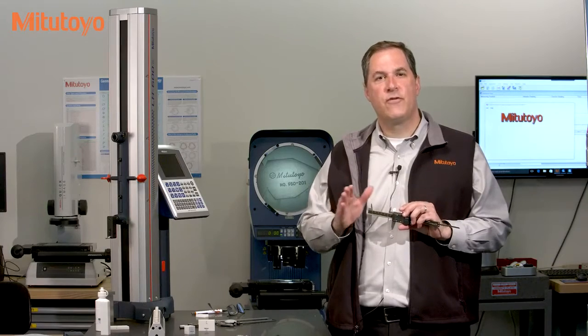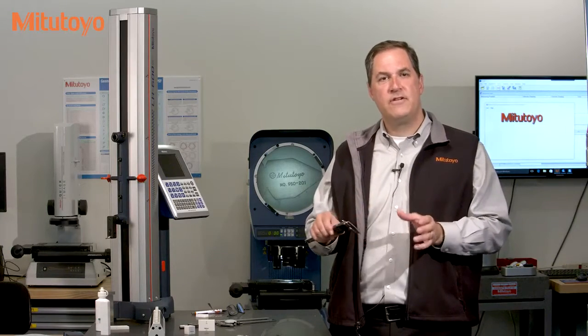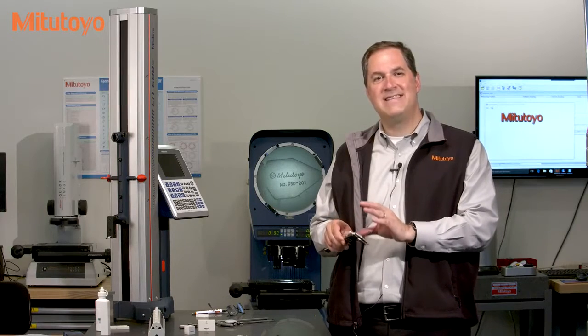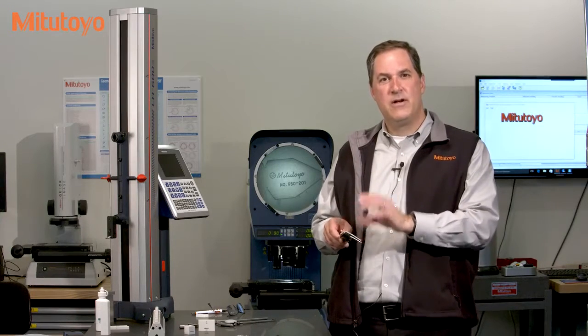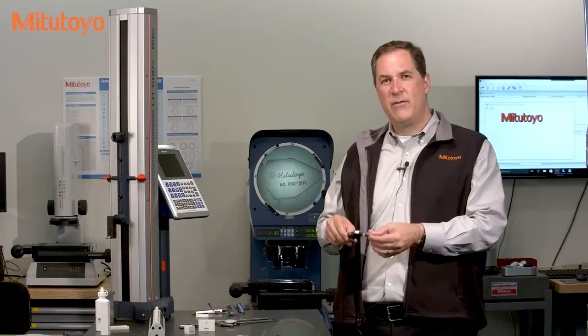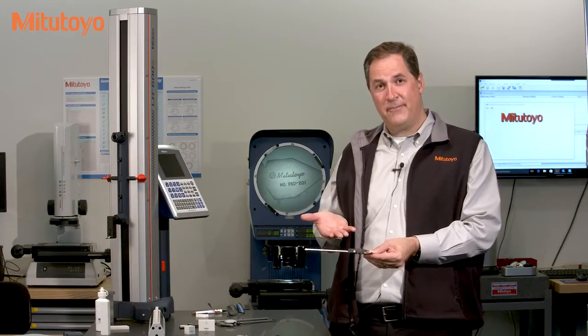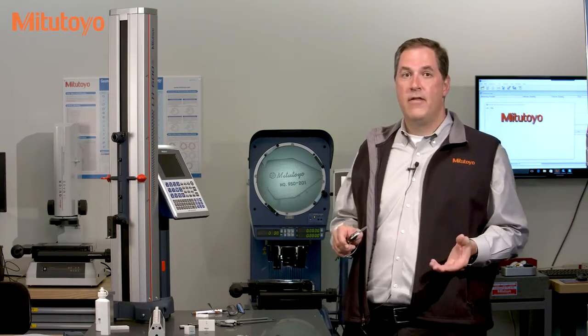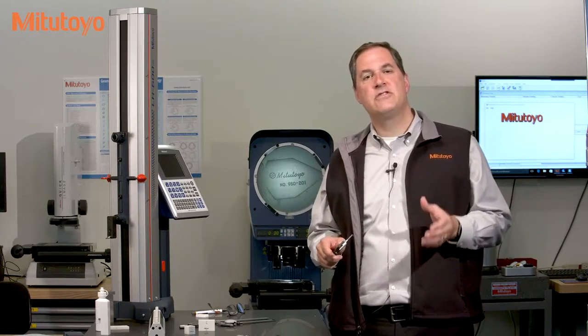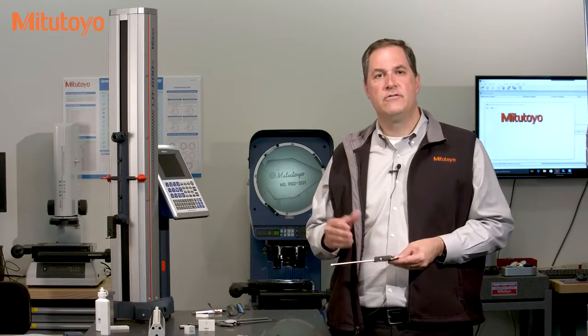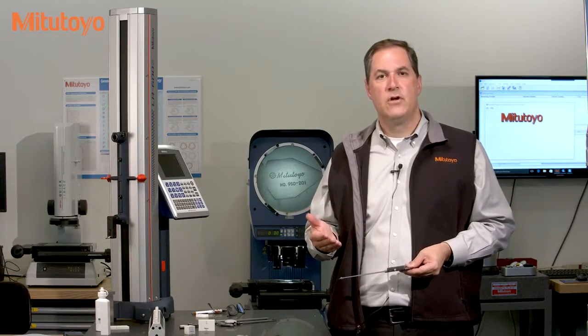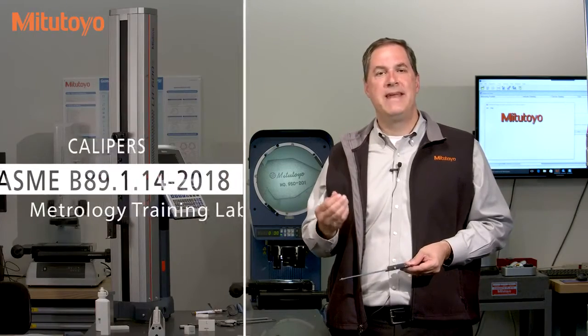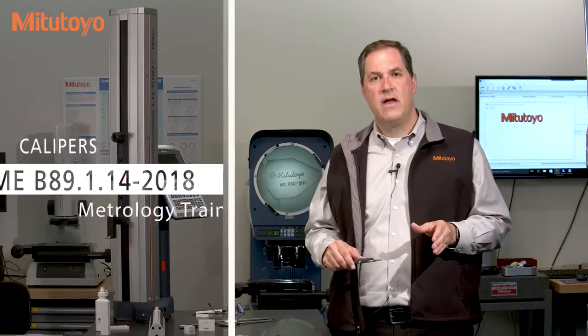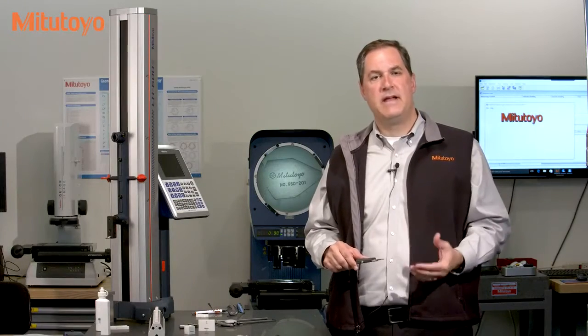Calibration is a search for errors, and we want to develop a calibration method that efficiently hunts down and finds any potential errors in the measuring instrument. So how do we best do that for a caliper? Well, there's a nice American national standard for digital, dial, and vernier calipers called ASME B89.1.14. And the calibration method that we'll be discussing is based on that standard.